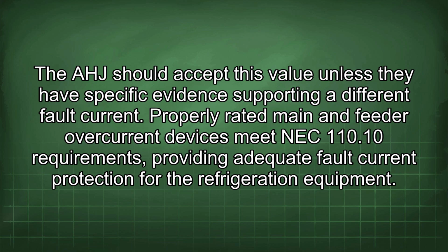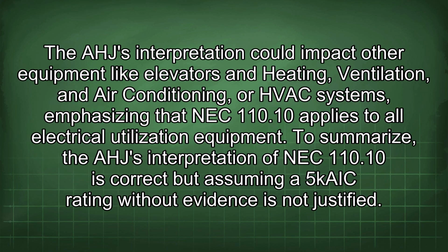Properly rated main and feeder overcurrent devices meet NEC 110.10 requirements, providing adequate fault current protection for the refrigeration equipment. The AHJ's interpretation could impact other equipment like elevators and heating, ventilation, and air conditioning, or HVAC, systems, emphasizing that NEC 110.10 applies to all electrical utilization equipment.